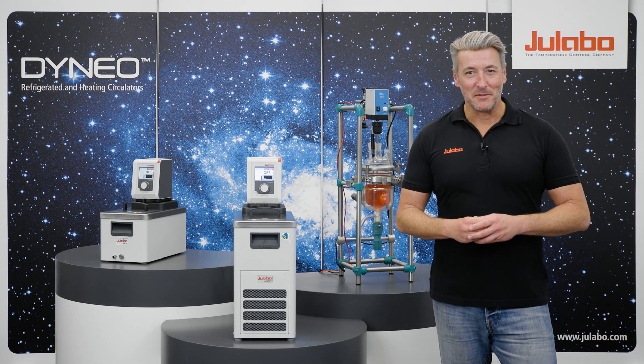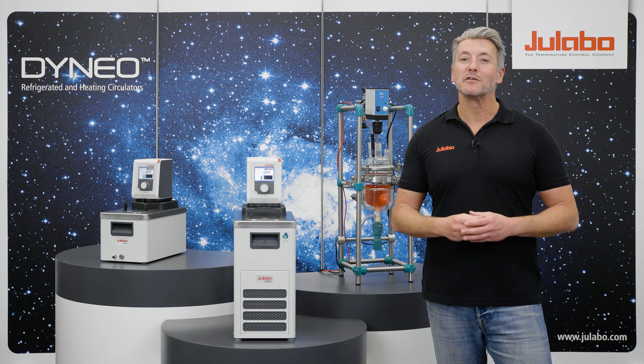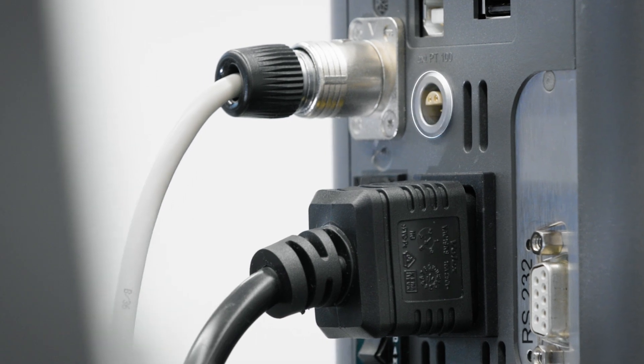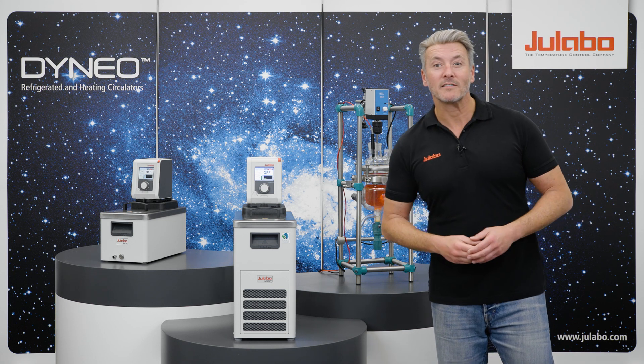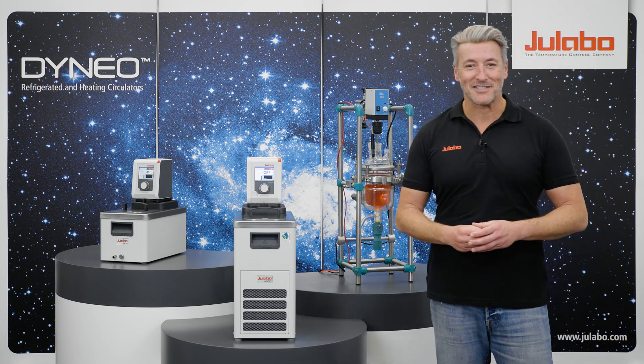Hello and welcome to Julabo. My name is Alex and today I will show you how easy it is to connect an external application to your Dyneo circulators. Dyneo units have an integrated connection for an external PT100 temperature sensor. This makes it the perfect match for a glass reactor application. In this case we connect the Dyneo to the primary circuit of a glass reactor, which then temperature controls a specific reaction.